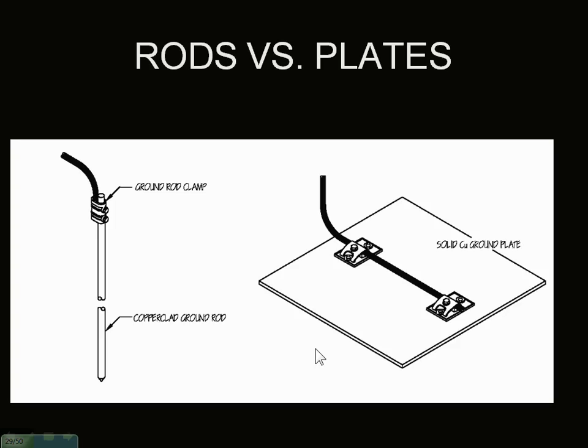The other thing you can do is drive a ground plate instead of a ground rod. It's not the preferred method, but like I said, if your house is located on a cliff and there's just no way to get a ground rod in, let's say you're sitting on 100 feet of bedrock, you can throw a ground plate in as well. That should disperse the lightning as well. This is just a ground test well. Basically, what you can do is place your ground rod in here, take this cover off, disconnect the ground, and actually do a 3-point fall-of-potential test on that ground rod to see what kind of ohm rating you're getting.